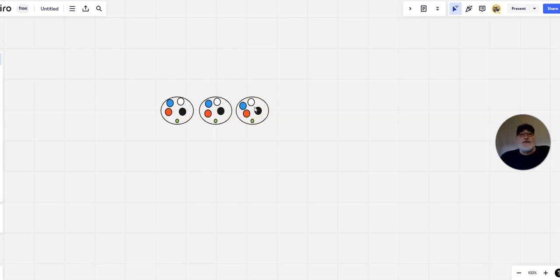A lot of times, to be able to get the amperages that we need, for example if you were building a 1200 amp service, you'd have to have four sets, a set being this right here, four sets of a grouping of conductors, which would be the three hots, neutral, and a ground, going back to your source point to give you your allowable current. So potentially four of these sets will equal 1200 amps. But this is an example of parallel conductors.